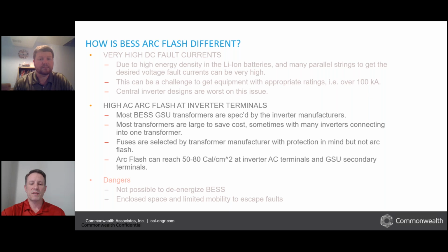We'll try to specify different fuses, but sometimes they're already in the field and they can't even be gotten to change them. So sometimes the arc flash can be 50 to 80 cals at the terminals. We usually try to get it below about 30, but sometimes it's not possible.